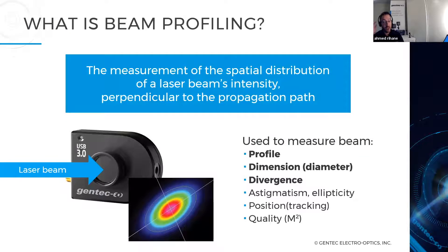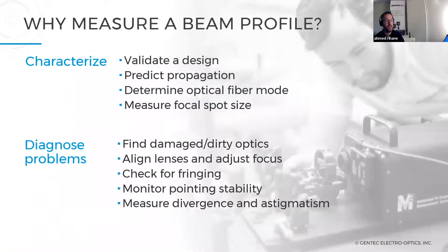Beam profile, as you may already know, is a measurement of the spatial distribution of laser beam intensity perpendicular to the propagation path. It's used to measure beam profile dimensions — diameter of the beam in X and Y, divergence, and other parameters. We measure beam profile to characterize and diagnose problems: hotspot measurement, fringing, monitoring pointing stability, etc.